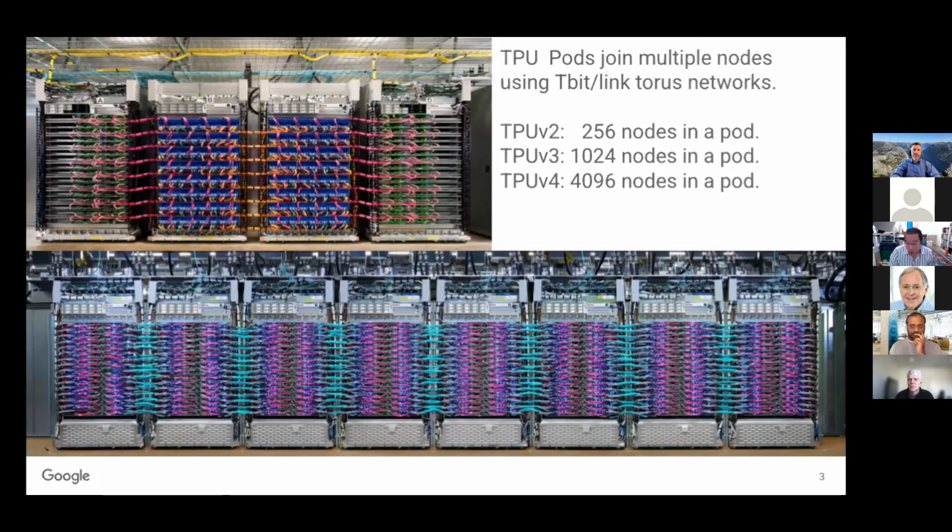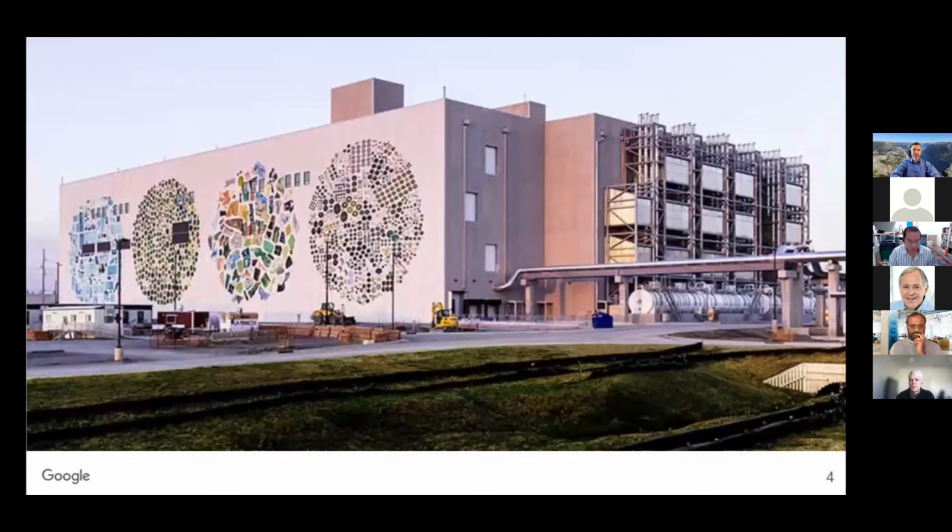And the scale of this is, of course, warehouse scale. I think Google touts warehouse scale computers, and this is one of our pretty data centers. I forget where this one's located. Normally I show this slide and say it's great that a data center can be pretty, but in the context of power, one of the questions is how many megawatts does a building like this represent? And it's tens of megawatts. I think our standard data center building at Google was 20 megawatts for a while. I think we're upping that now and building 30s and 40s and maybe even 50s.